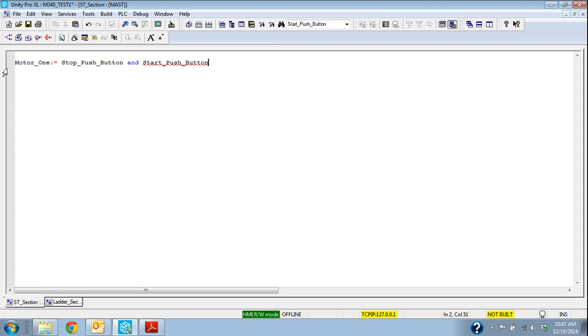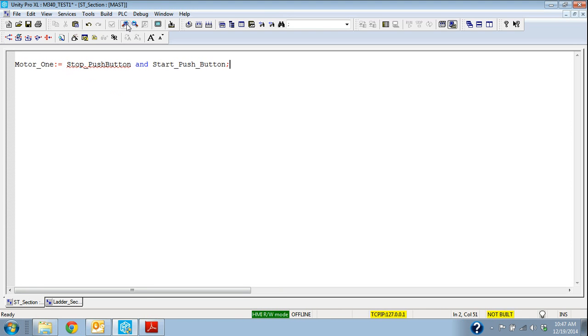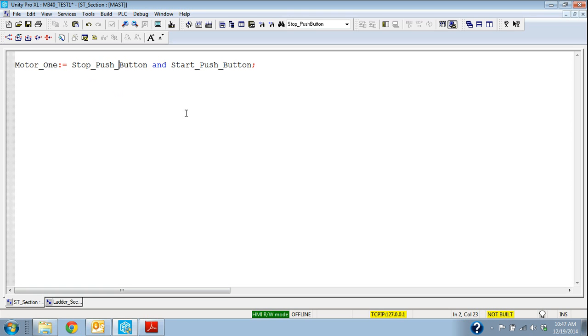And then any of the structured text statements the line needs to end with a semicolon. And if something's not right, if we don't spell this right or the variable is actually not in the list, so I took that underscore out of there you can see that it puts this red line. Let me zoom in a little bit so you can see that. So if I don't have any lines, everything goes away and it looks good, then I can tell as I'm typing the statement looks good.